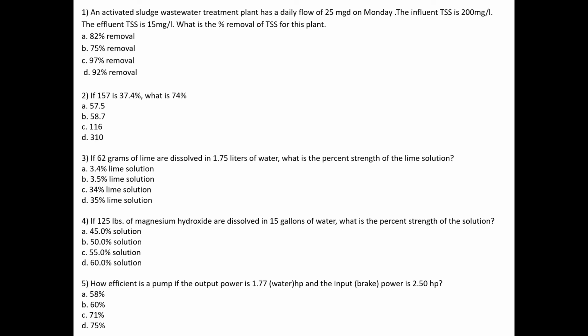It's not floating in a vacuum, just spinning. So the input power to the motor is the motor horsepower. The input power to the pump, which is also the output shaft power on the motor, is the brake horsepower. That's how much horsepower has to be applied to that pump to move that water. And the lowest horsepower is the water itself in motion.